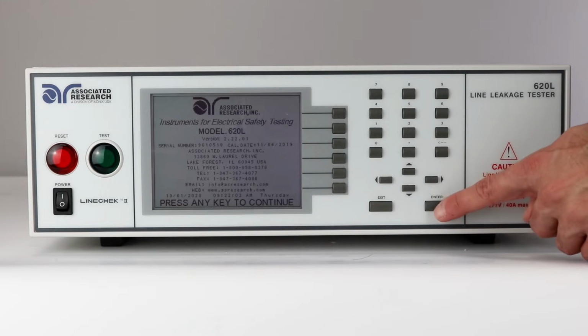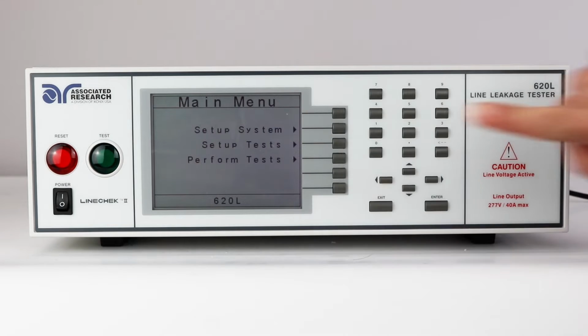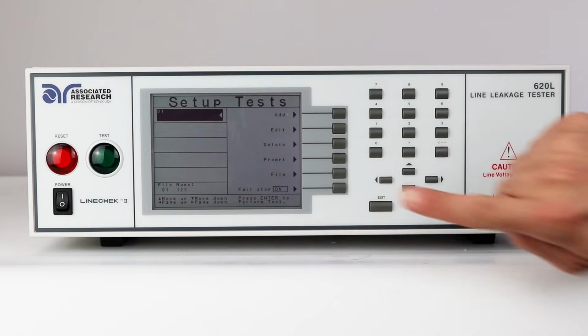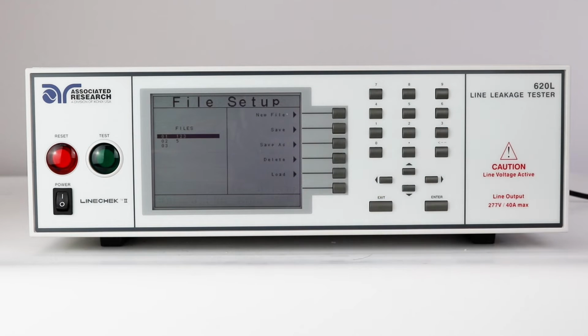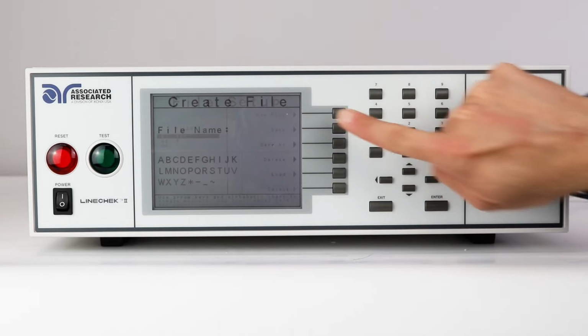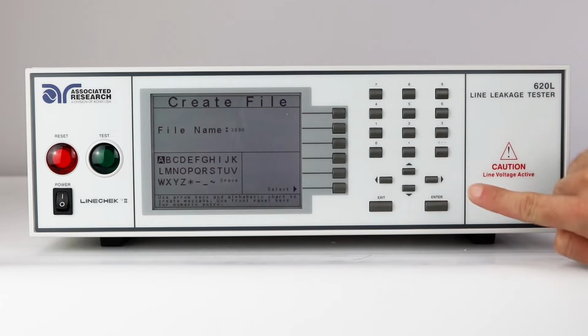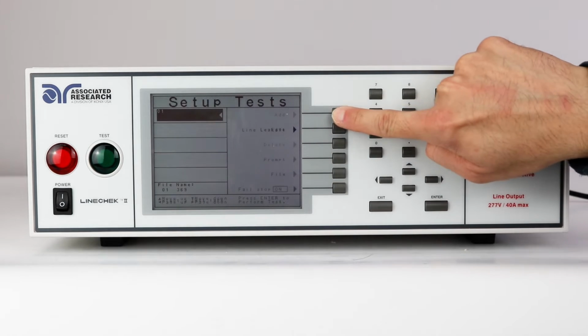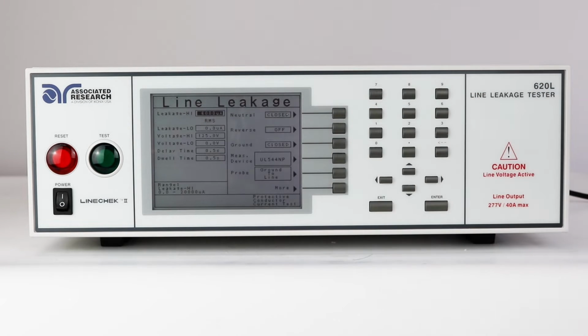After powering on, press any key to navigate to the main menu. To set up a line leakage test, press the Setup Test key and then press the File key. You will first need to set up a new file. Press the New File soft key and use the alphanumeric keypad to enter a file name. When finished, press the Enter key, press the Add key, followed by the Line Leakage key. This will take you to the line leakage parameters window.